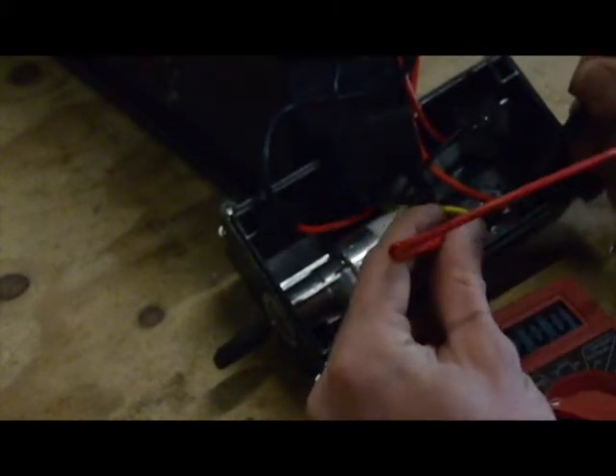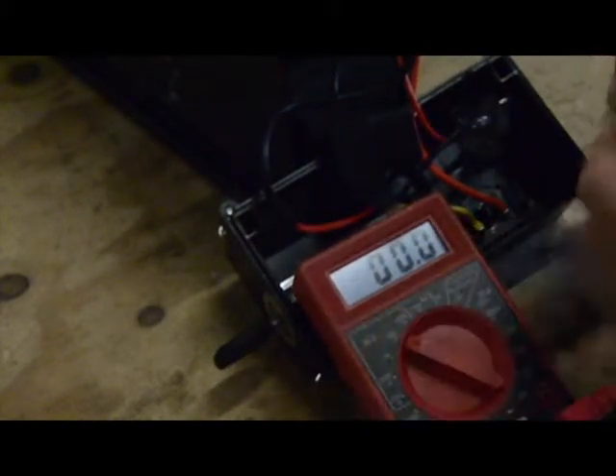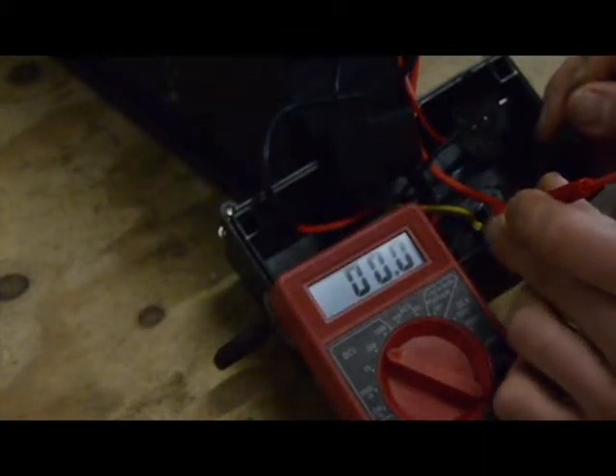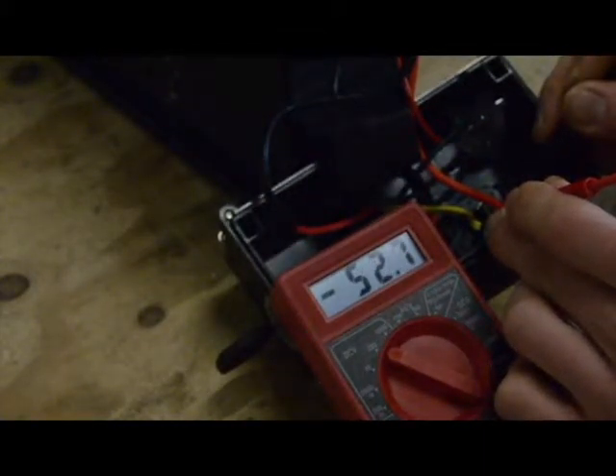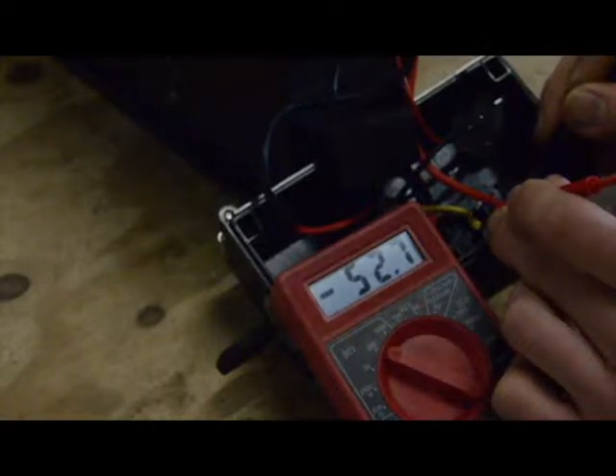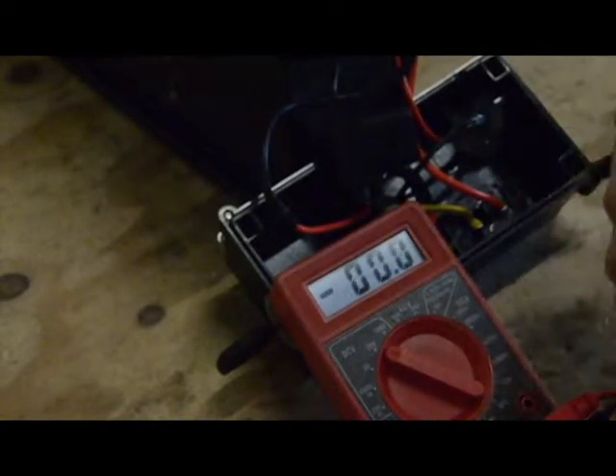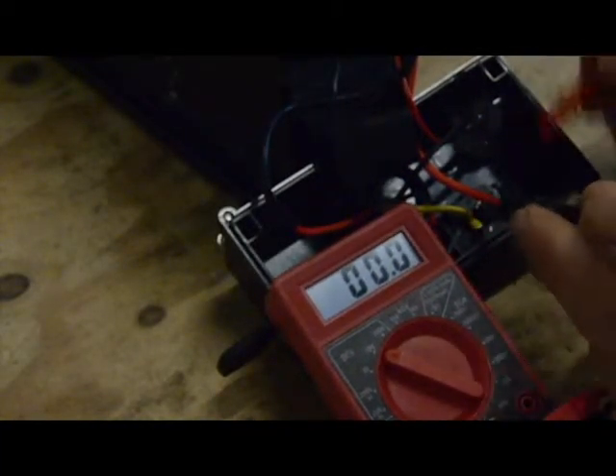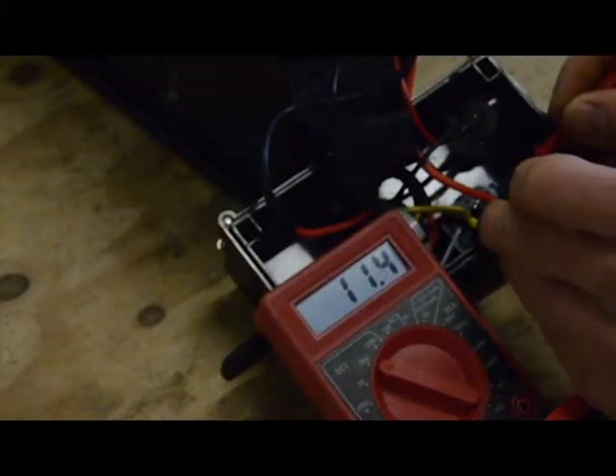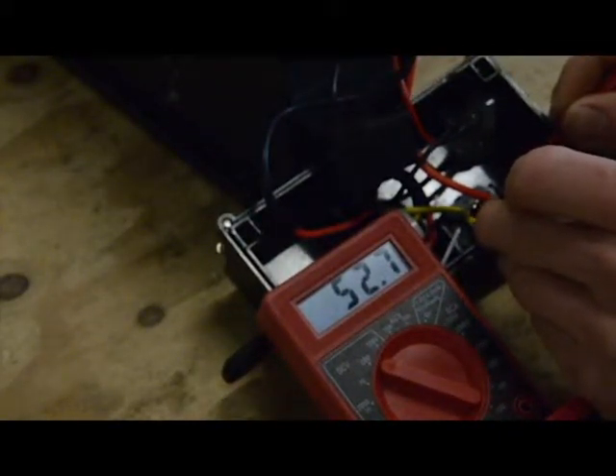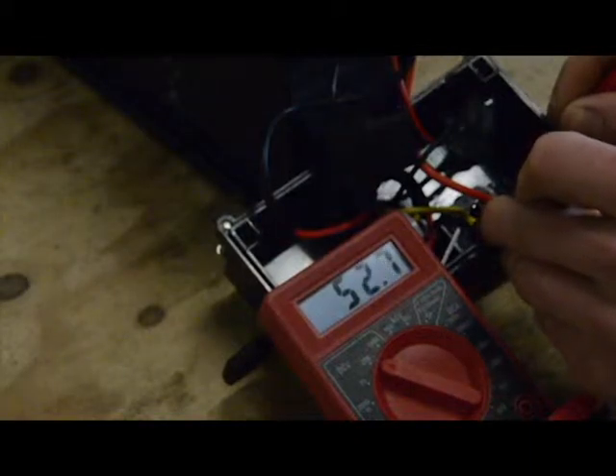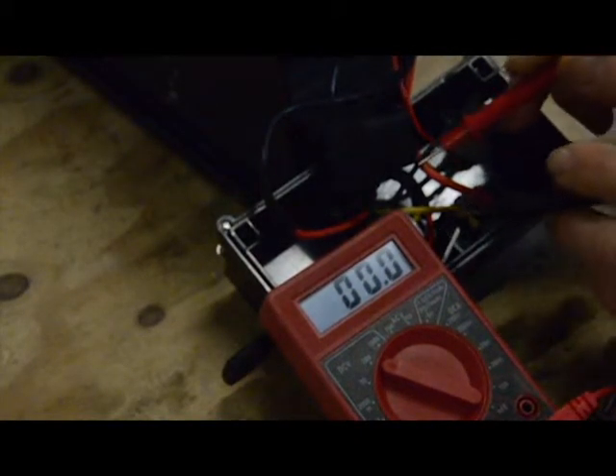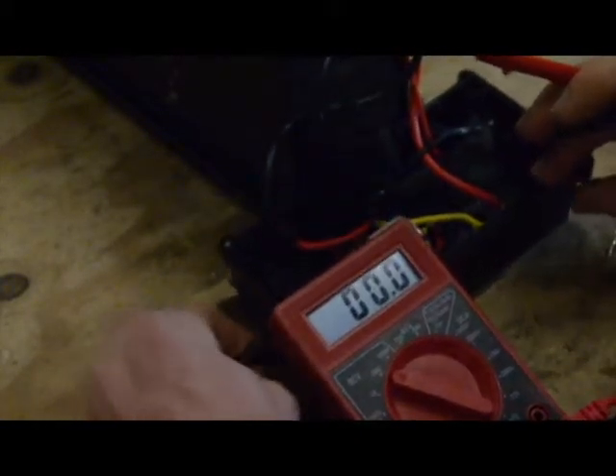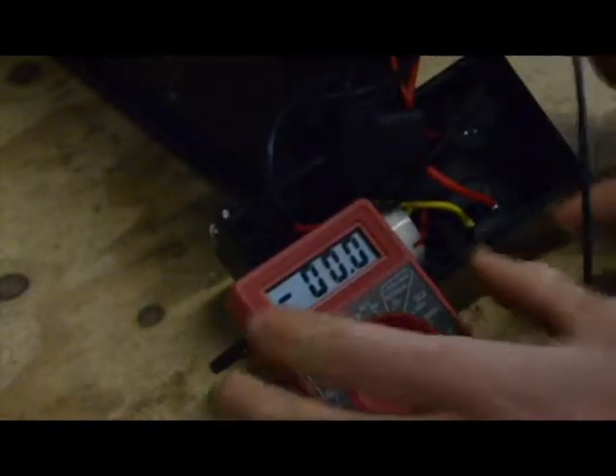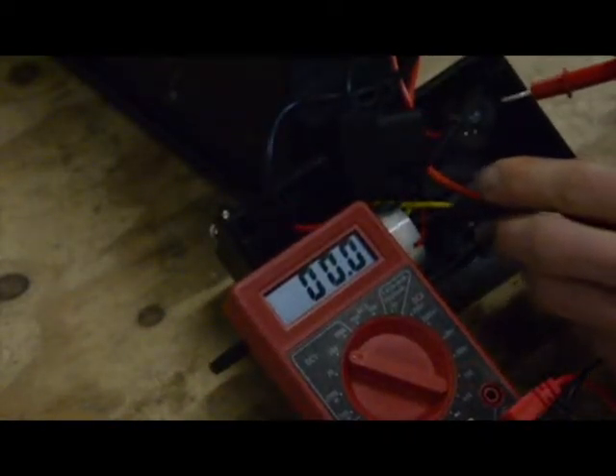So if we wanted to see if our discharge contacts are maybe having a problem, if we can't read good voltage on the outside, we can read them from the inside here. You see we have 52 volts. Note that I have my leads reversed there, so red is red and yellow is black here. 52.7 volts, so that looks pretty good. If that wasn't looking right, we'd follow it back a little further, make sure that our key is on, and we can measure it at the input for the switch.